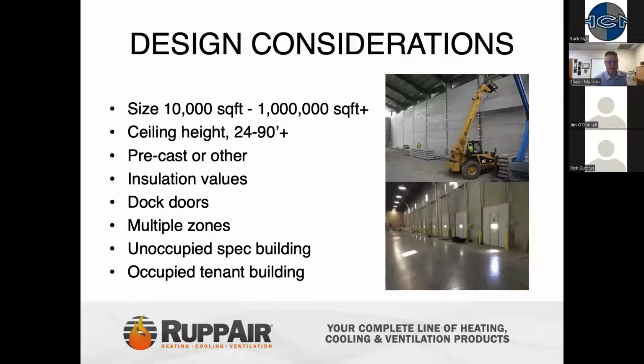So the design consideration when looking at these big box type facilities is understanding the size. These are all the things we're going to have to understand before we get into the design criteria, but the size of that building. With these big box type heating applications, you're dealing with buildings anywhere from 10,000 square feet to 1 million plus. I personally have done them up to about 2 million square feet. Ceiling heights, 24 foot to 90 foot. Commonly, if you get some of the automated racking systems, you're going to have some high bay areas that might get into that 70 to 90 foot range in height. So make sure you understand that criteria.